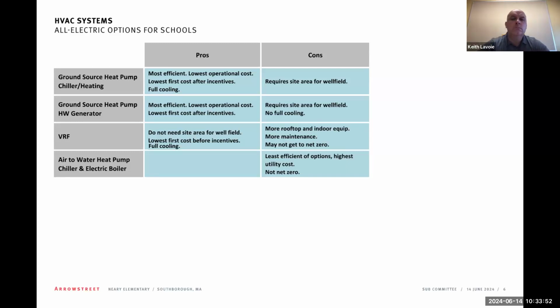Okay. Even going back to our Hillsborough project, which opened in 2021, Larry will probably remember, that didn't get to full net zero, but they did put that system on. I'd say it's a mix of ownership and PPAs, probably more PPAs than ownership. When you say PV ready, you allocate the roof space, you incorporate your structural for the supports for the panels, run the conduit for the electrical, right? Yep. Reserve the breakers and the space in the panels. Okay. Yeah, you almost go to a percentage and you're almost there. You might as well just benefit the points and get the energy.